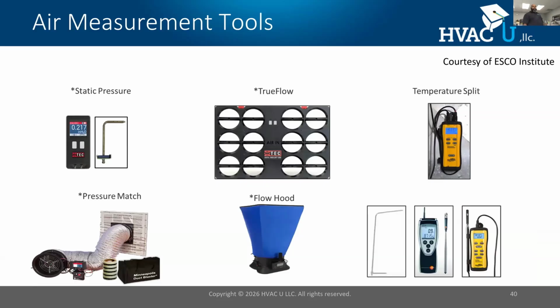Here are some of the tools that you can use for direct airflow measurement. Now, static pressure, we'll talk about each of these and some of their benefits, but the moral of the story, you want to measure airflow. With duct problems, you can only find out what the problem is if you have the data to support what the duct issue is. Okay.